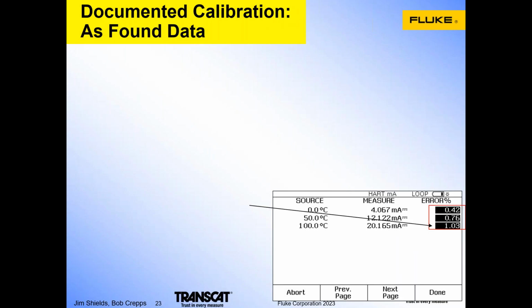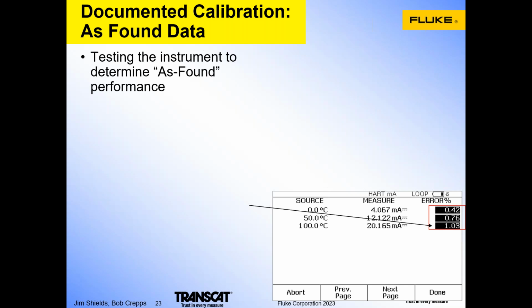Once the calibration is completed, the as found document is being prepared in the calibrator. You can see the temperatures that were sourced, the milliamps that were measured, and the errors as percent of span.